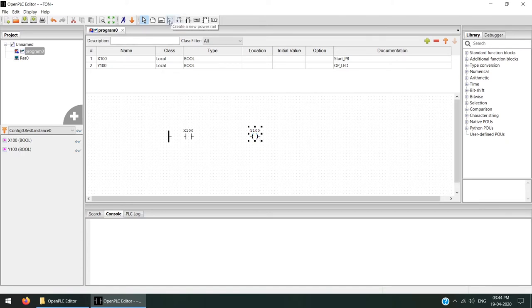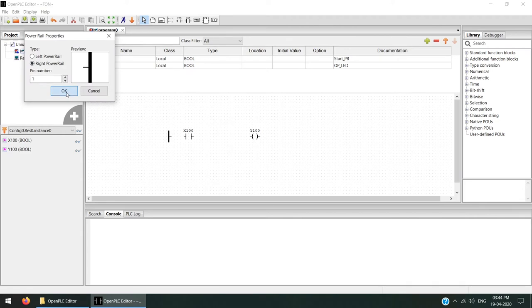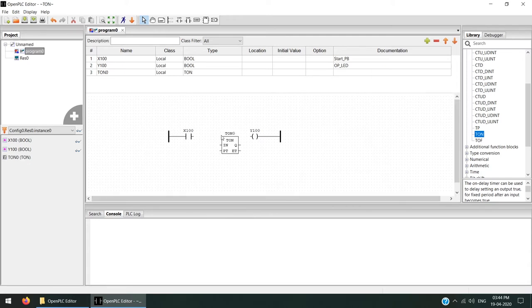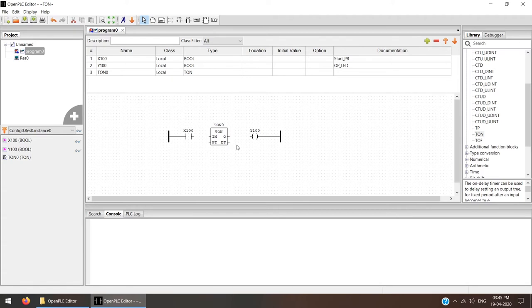We need to add one more rung here — it will be the right rung of the single ladder. Click, drag it, and place it at the center. We are using the function timer on delay: if I press the push button, after some delay we get the output, otherwise no output. For that, go to the library under Standard Function Blocks — at the second last position, TON timer on delay is there. Click and drag it. You get the function block with four pins: IN is input, Q is output, PT is the set time, and ET checks elapsed time.